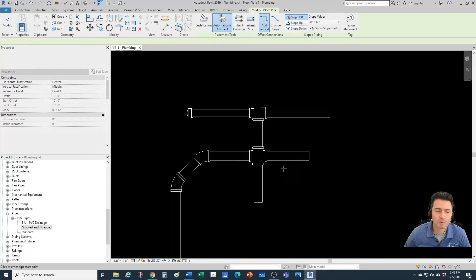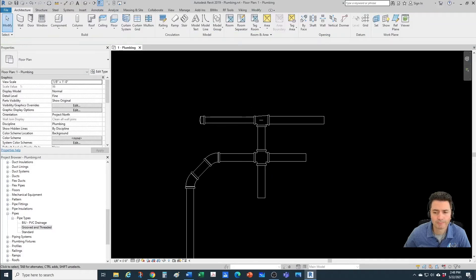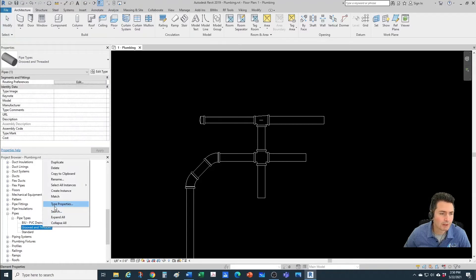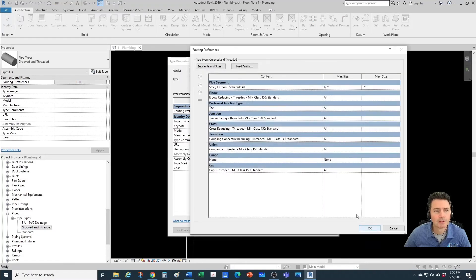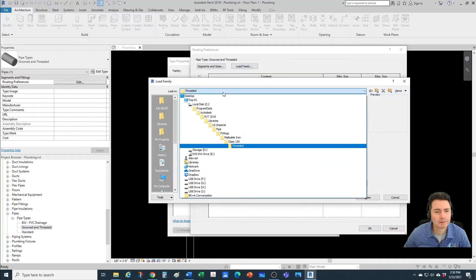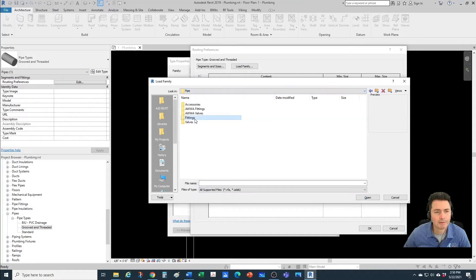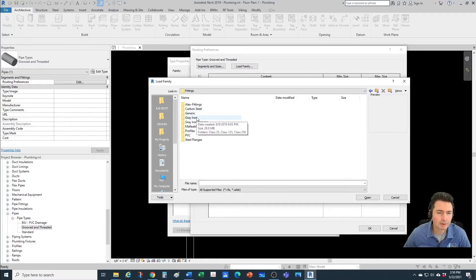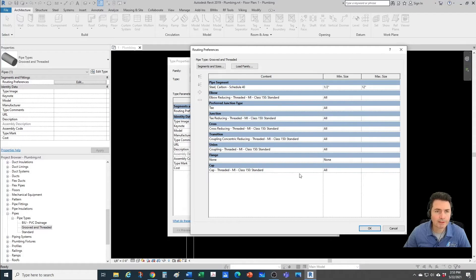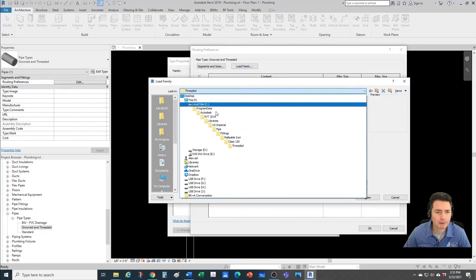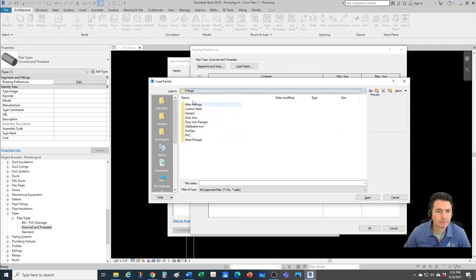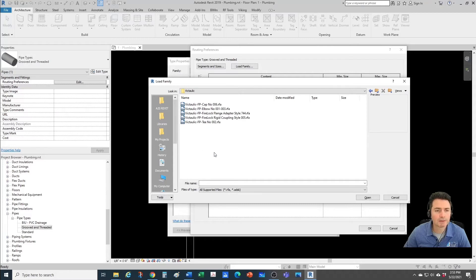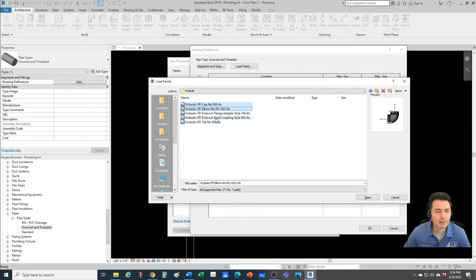Now let's tackle the grooved part. If you try to load those families from the out-of-the-box families in Revit, under Pipe Fittings you'll see there are no groove fittings available — you have to go to Grinnell or Victaulic and download those families. I've already downloaded some, so let's load them into the project. Under fittings I have them in a separate Victaulic folder. For now let's bring in the cap, the elbow, maybe a coupling, and a T.